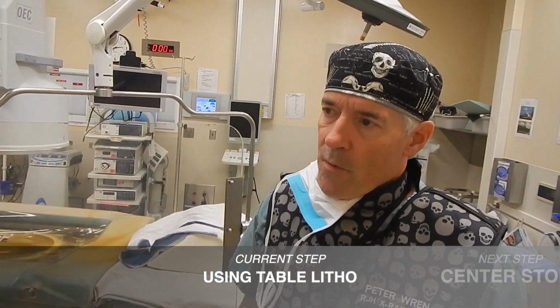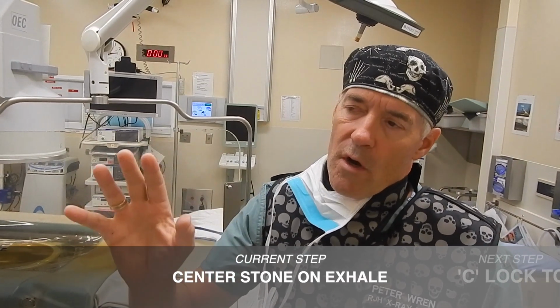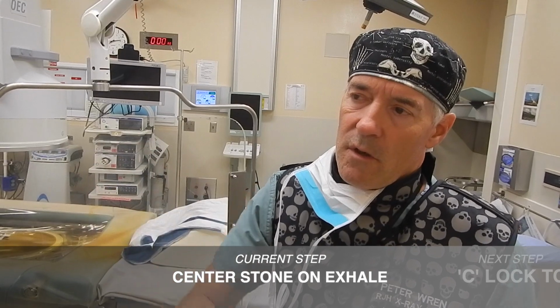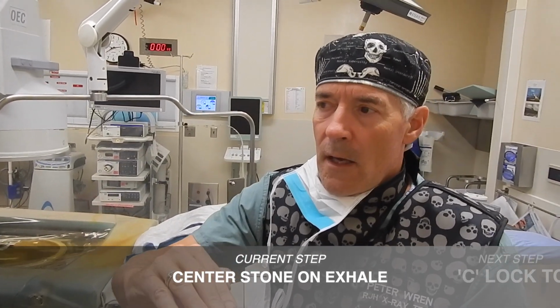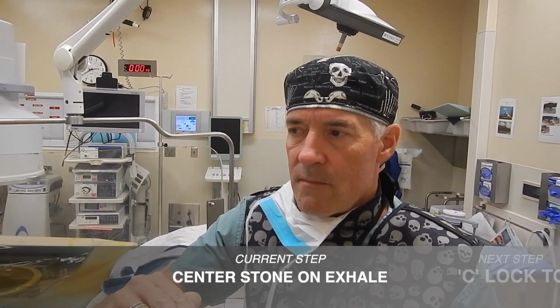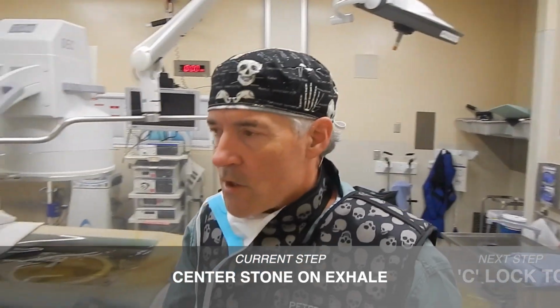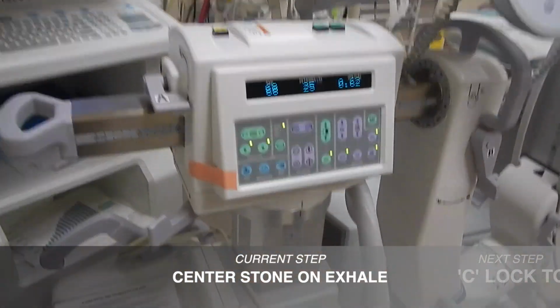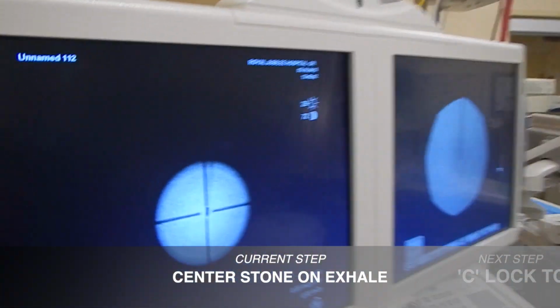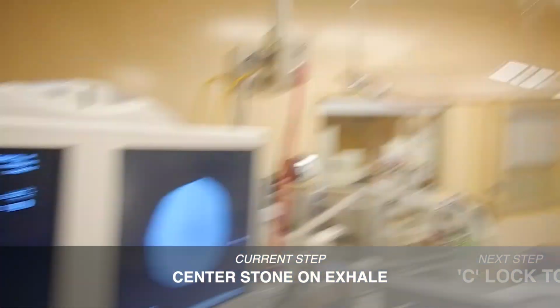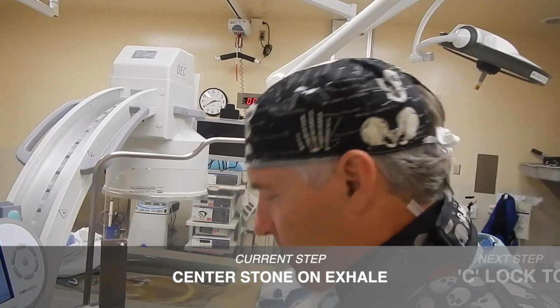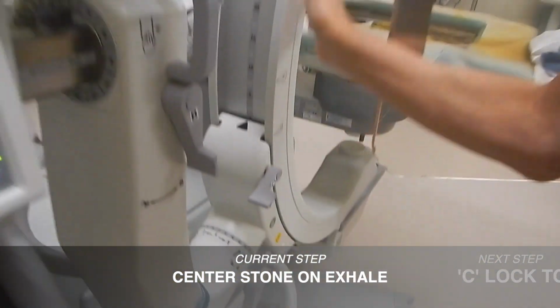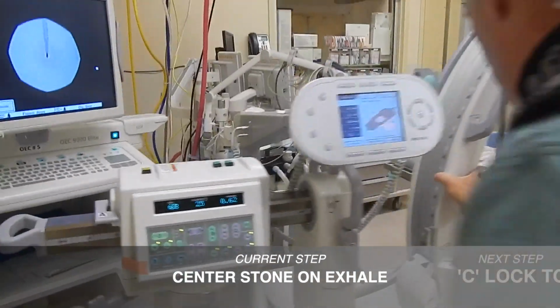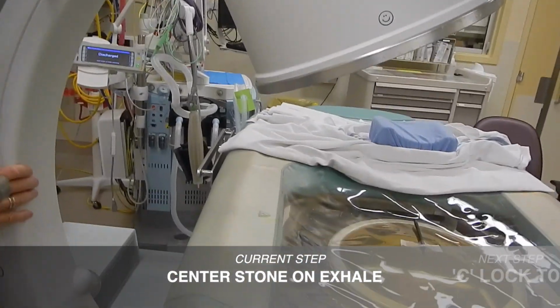The thing you have to watch for is the patient's still breathing, so you have to watch fluoro long enough to see where the stone's going to rest when the patient exhales. It'll sit there for a good amount of time to get as many shocks as possible. So you just watch that, and then you save that image. You don't have to swap it, but the one on the right and that one, and a couple more that I'll tell you about, you're going to want to send a few later. So once you have that, check. It's very important, and that's the positioning earlier. So you just tell that position for the lock.